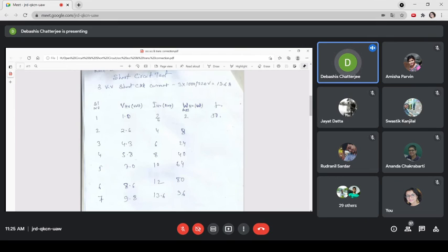2, 4, 6, 8, 10, and accordingly how much voltage is required, they have adjusted through the variac, right? And then they have read the wattmeter readings, 2, 4, 6, like that. Up to 13.6, that is the high voltage side rated current, 100% value of rated current. They have got 9.8 volts and then 36 watt. A three-phase transformer is not used, so they have made it for all, so that is why it is there.